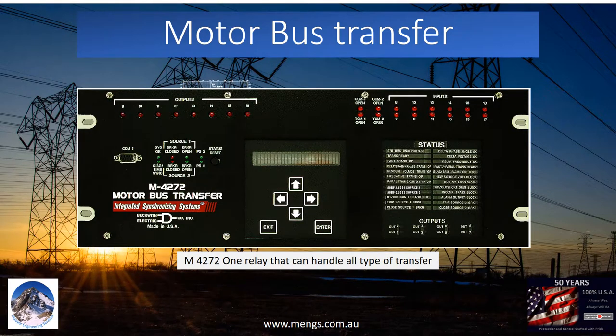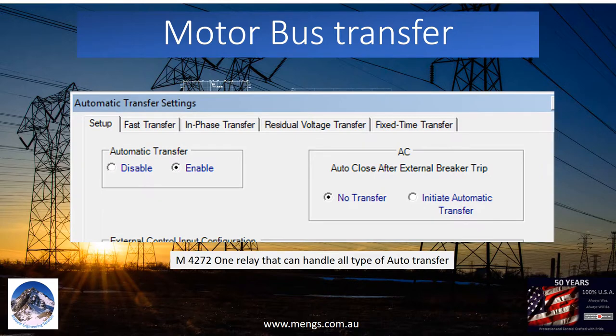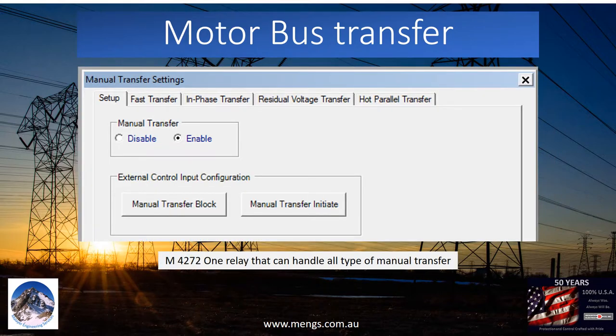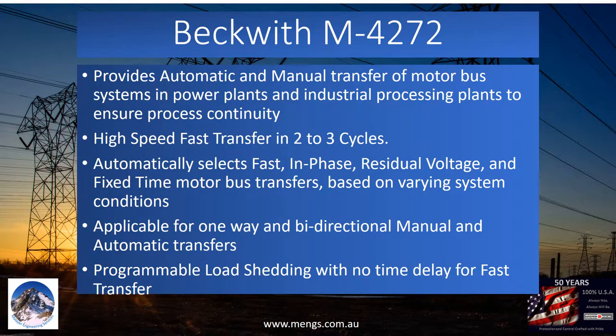The Beckwith M4272 is an advanced motor bus transfer relay. It provides very fast sync check of less than 10 milliseconds. The Beckwith M4272 can handle all types of auto transfer: fast transfer, in-phase transfer, residual transfer, and dead transfer. It can also provide manual transfer. Make-before-break, or hot paralleling, is a feature that may be required for seamless manual transfer. The M4272 provides automatic and manual transfer of motor bus systems in power plants and industrial processing plants to ensure process continuity.